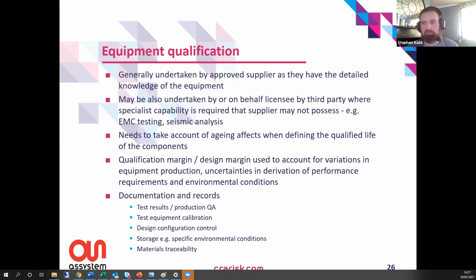They may well be within tolerance, but it takes account of all of that. And ultimately, the evidence that comes out of the qualification process will be a whole host of records and documents. It could be things like test results where we've undertaken specific testing. It could be production QA, where there's quality checks undertaken during the production process to confirm that everything's okay. If we are relying on testing, we might need to see equipment calibration, test equipment calibration records, to show that the test equipment was appropriately calibrated when the tests were undertaken, so that we can have confidence in the results.